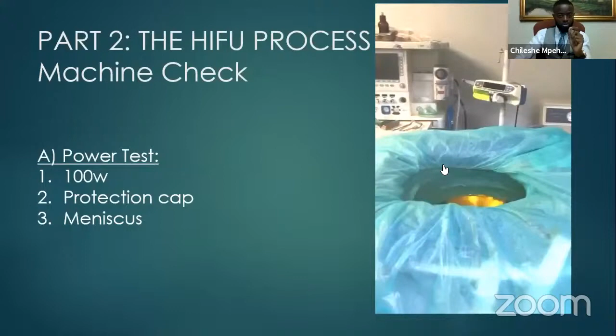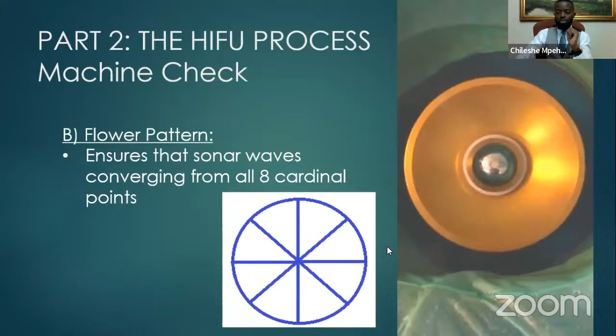Okay. We then do what we call the flower pattern test, and what you're seeing here is the piezoelectric plate. We are shooting the sound waves, and we want them to converge at a focal point right here. And what we have here is a diagrammatic representation that we want the focal point to be the place where each area that is shooting is sending the sound waves in a straight direction to meet at one point. If that happens, you get this image that you just saw there. So you get that pattern, which is a floral pattern, and that is what we call the focal test, the flower test.